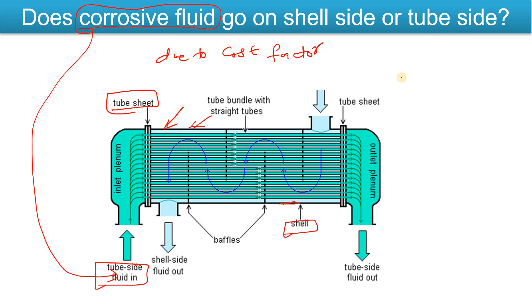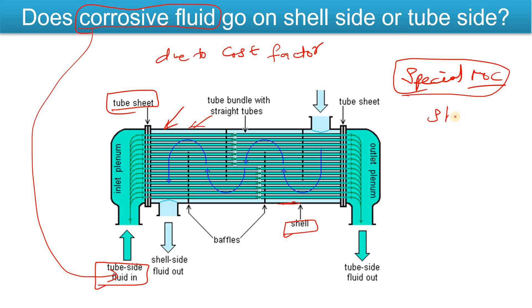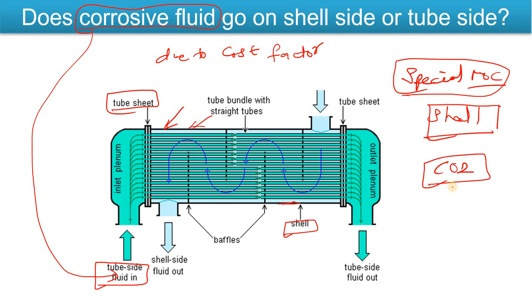That's why corrosive fluid should go in the tube side rather than the shell side. For the tube side, you will need to use a special MOC (Material of Construction) that prevents corrosion. If you flow it on the shell side, you would need that special MOC for the entire shell, which increases the cost significantly. For example, in a CO2 compressor, the CO2 most of the time goes in the tube side rather than the shell side.